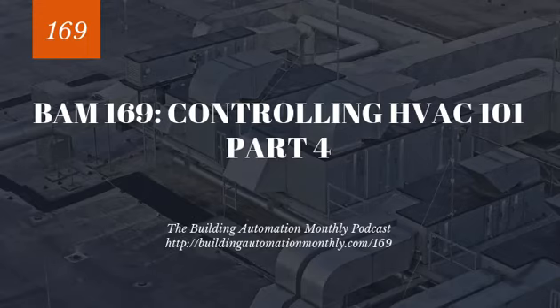And when you turn on boilers, you typically need to slowly warm them up, and this will tend to affect secondary control, morning warm up, and multiple boiler setups. So when you're approaching boilers, it's not like a chiller where you just turn it on and it starts to run. You typically have boilers that will go into low fire, then they'll go into high fire, and they'll start to just gradually warm up. Otherwise, you shock the system.